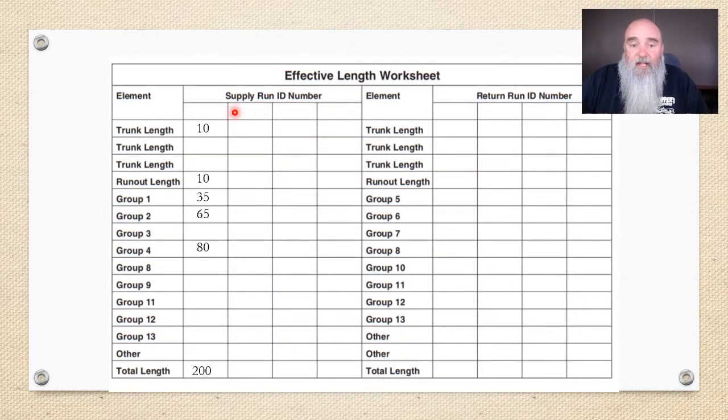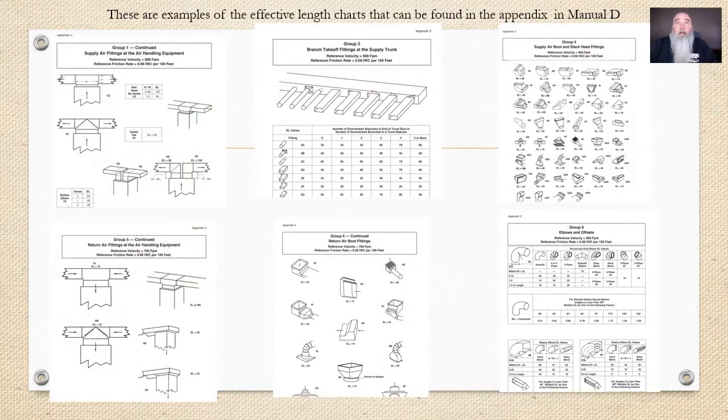And if you've ever filled out the effective length worksheet, this is part of the process of doing a Manual D calculation. Well, there it is. These are examples of the charts that you'll find in Manual D, and they are grouped. Let's see, this is a supply, so the reference velocity is going to be 900 feet per minute. This is a supply, reference velocity is going to be 900 feet per minute.